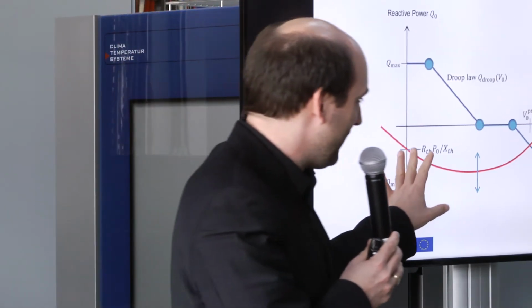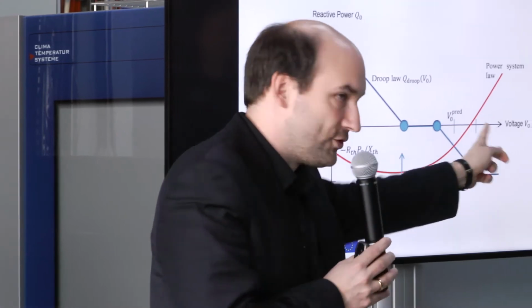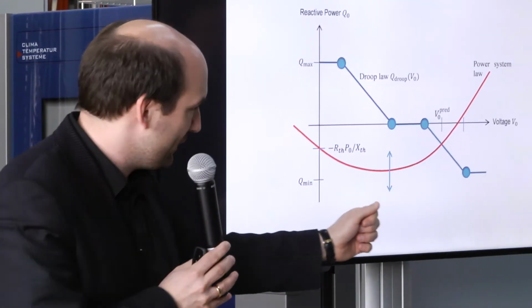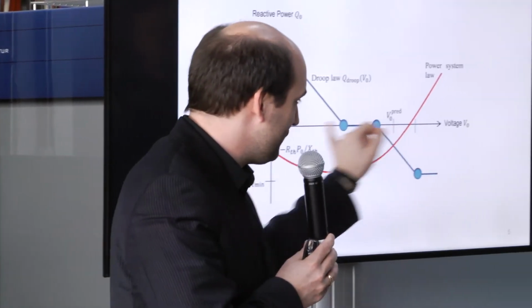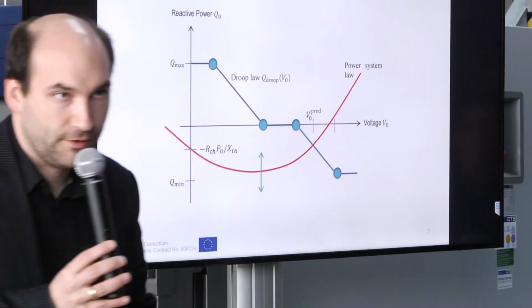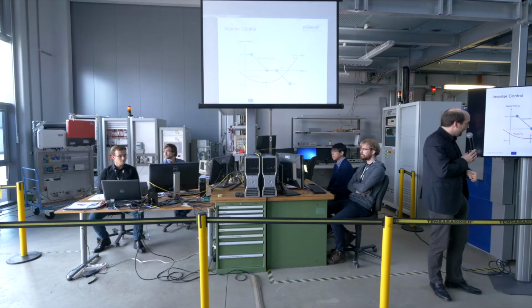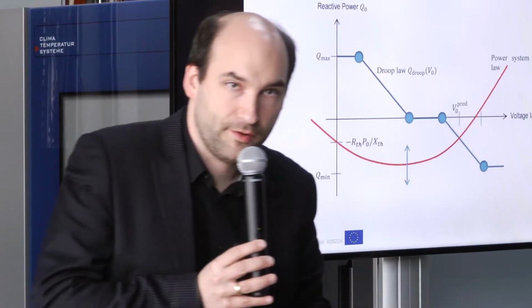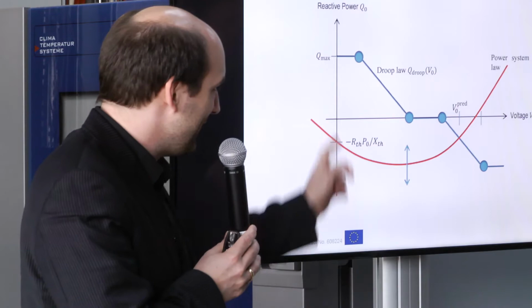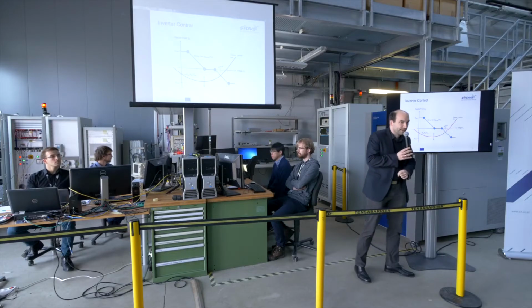This chart basically shows the voltage at the feeding point of the PV unit. As this changes over time due to fluctuation of generation and load, the PV locally decides on the amount of reactive power fed to the grid or taken from the grid based on this curve. It's a Q of U function, implemented in the inverters.